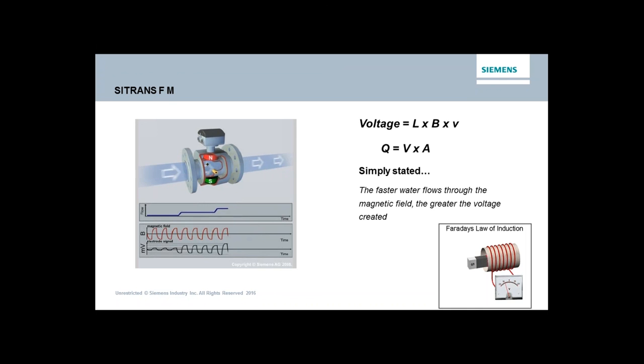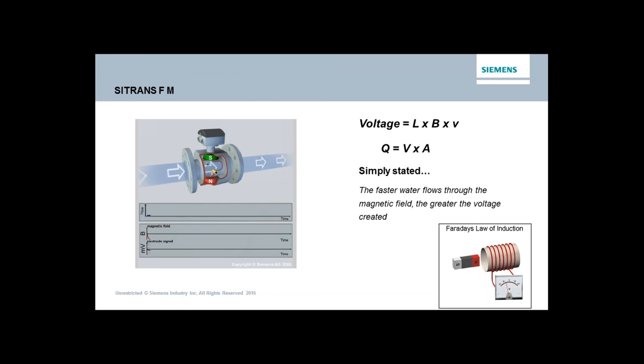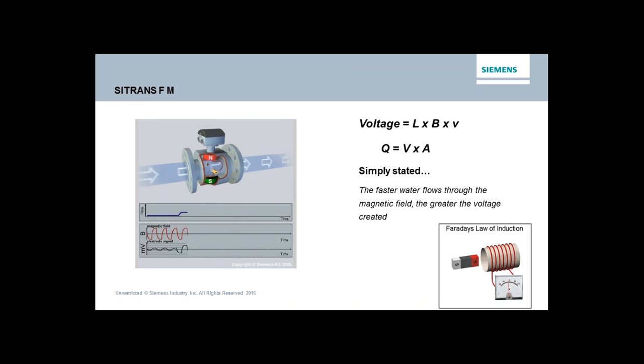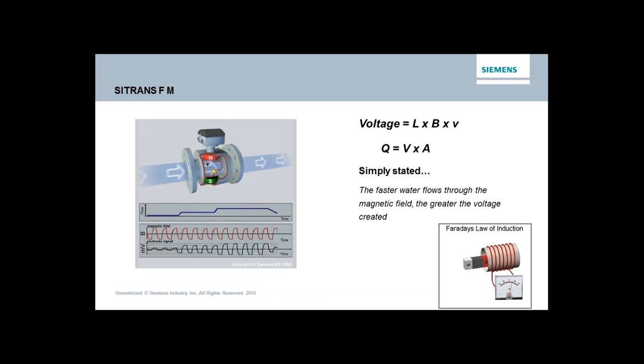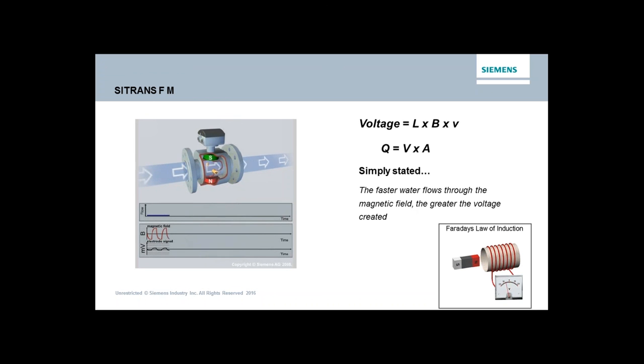What the change in conductivity does is simply increase or decrease the strength of that signal. What we're concerned about is measuring the velocity. If you take velocity and you have a known area — and because these are inline meters with a fixed diameter tube — we can convert velocity to volumetric flow rate. At the end of the day, we don't care what the density is, we don't care what the viscosity is, and we don't care what the conductivity is, assuming the conductivity meets the minimum threshold.